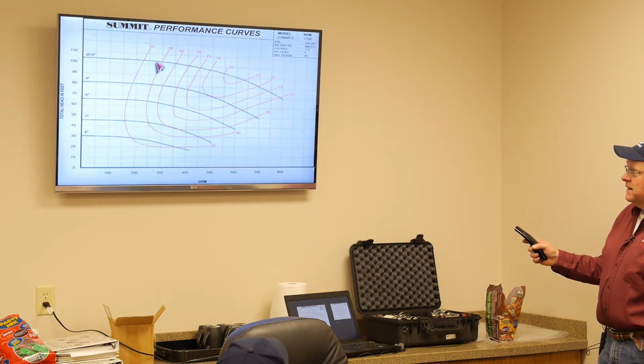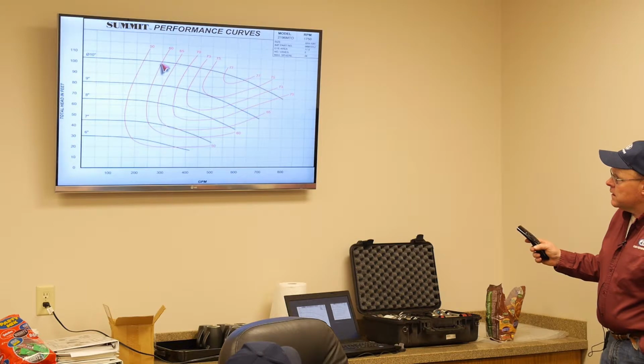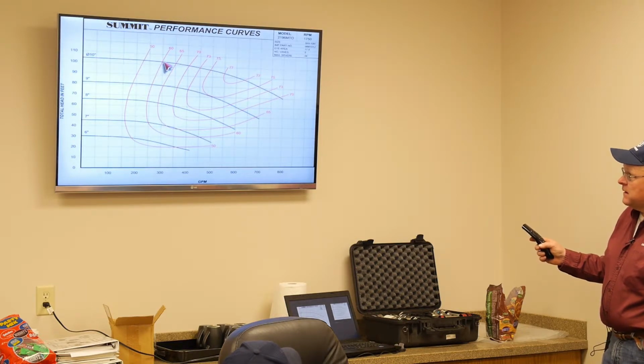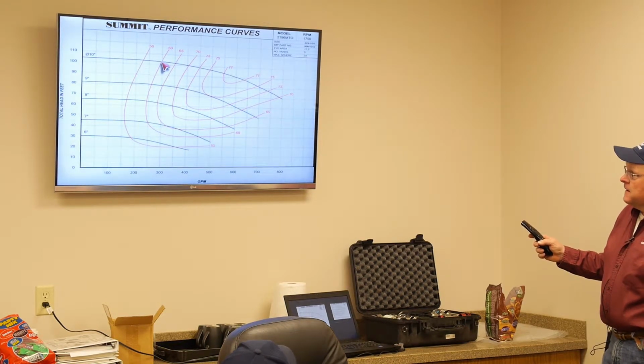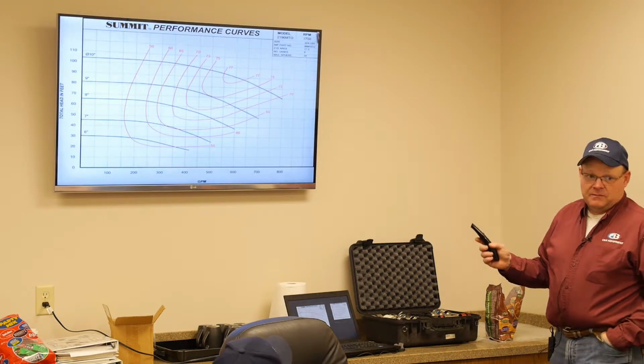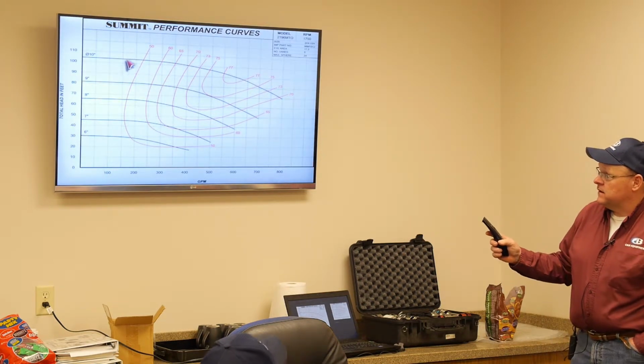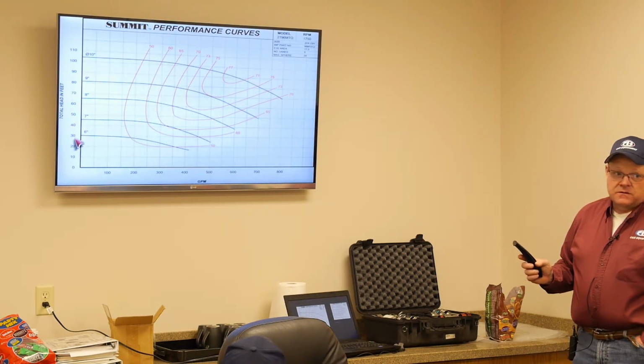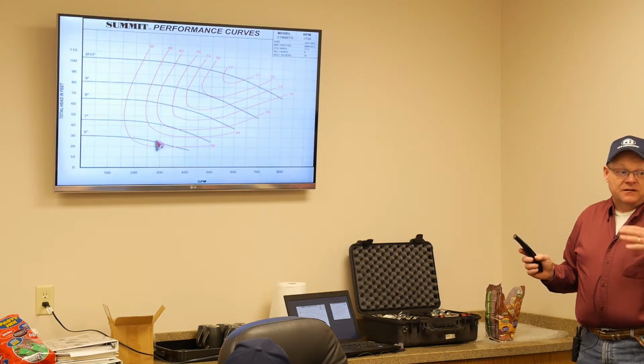If we're running over here, it's ugly. In other words, we're running at 300 gallons a minute at 105 feet, which is about 45 pounds, right? So what's happening internally in the pump? If we're running all the way over here to the left, what bad effects are we getting in the pump?